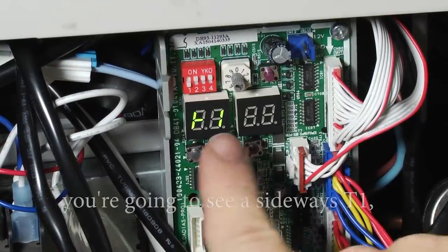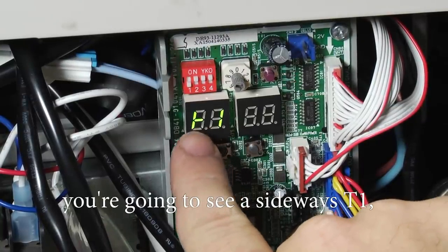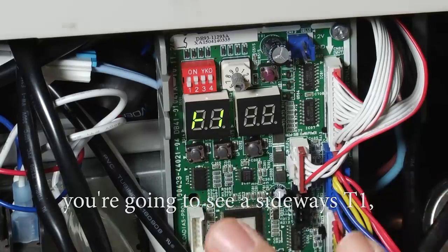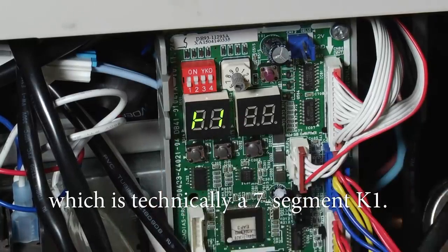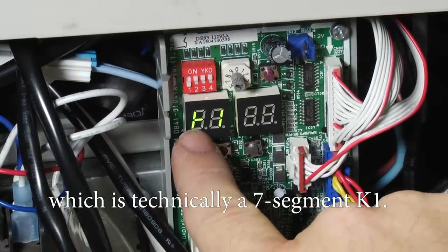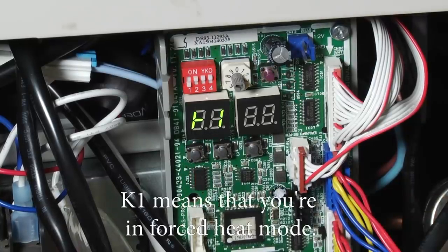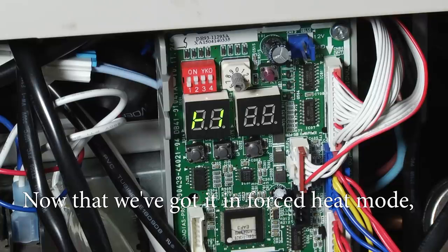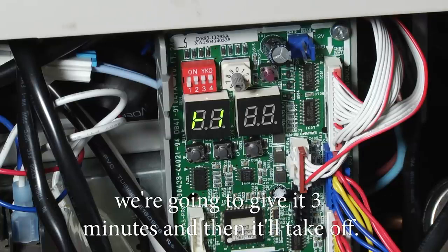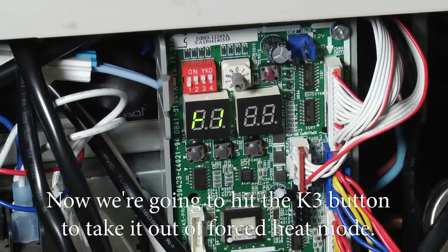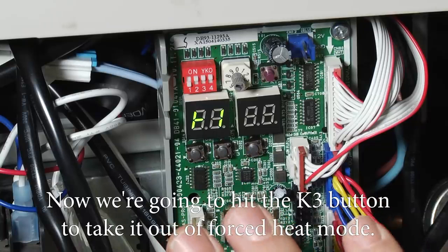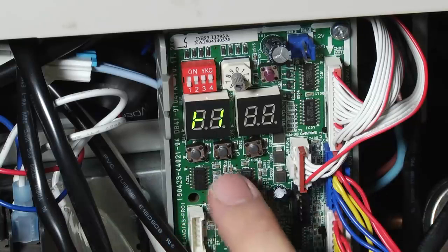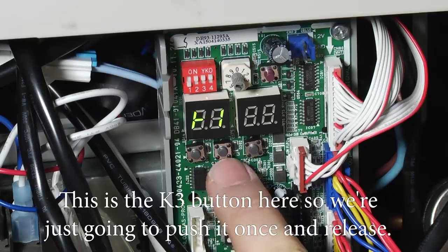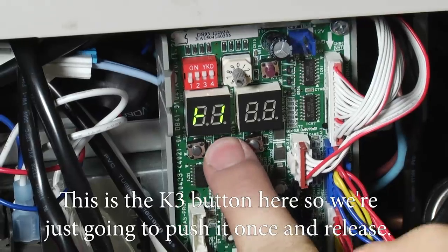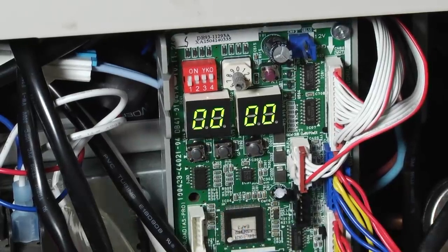So when you hit the button, you're going to see a sideways T1, which is technically a 7-segment K1. K1 means you're in forced heat mode. Now that we got it in forced heat mode, we're going to give it 3 minutes and then it'll take off. Now we're going to hit the K3 button to take it out of forced heat mode. This is the K3 button here, so we're just going to push it once and release.